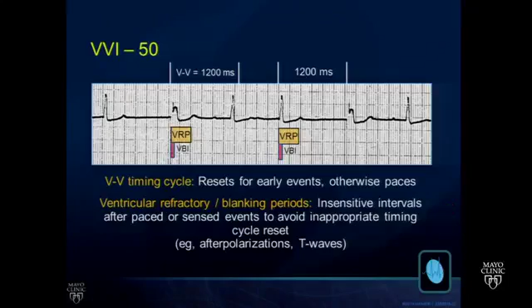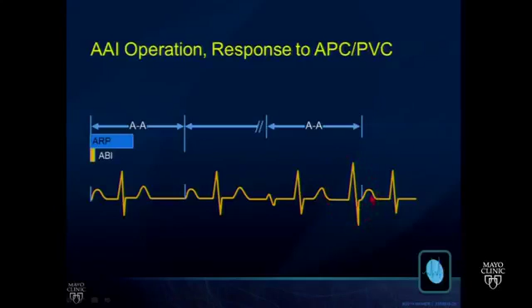The board may try to trick you with an AAI tracing and show you this type of scenario where you have a PVC before the completion of the atrial time clock and then a spike on the upslope of the T wave, trying to tempt you into thinking that ventricular undersensing is present. But remember, this is an atrial lead, there is no ventricular lead, and so the brain of the pacemaker can only respond to what it sees in the atrium. So this would be an example of normal AAI operation.